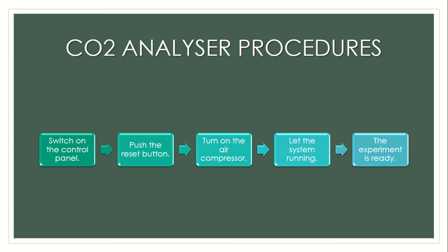And then after that, check the control panel, which is QT401 and QT402, achieve the constant value. Next, we have to push the reset button, which is at the QT401 and QT402 on the junction box for about 2 seconds.